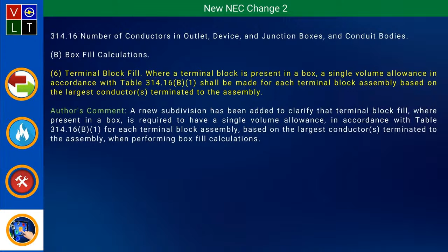The thing I like about this one, what they did, this is box fill calculations, and they added a new item number 6 where they talk about terminal block fill. They're saying if this is present in a box, it's required to have a single volume allowance, and that allowance is based on the largest ungrounded conductor, or the largest conductor, that terminates to that assembly. So you'd have to add one more to that if you're doing the calculation with a terminal block in it. That's probably good, it was just something that needed to be there.